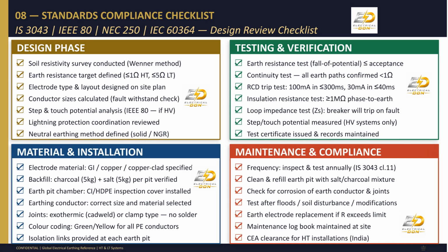Our compliance checklist covers the design phase, material and installation, and testing and verification. Key items include soil resistivity surveys, defining resistance targets, ensuring correct conductor sizing, proper backfill material, and mandatory annual inspection and testing to maintain safety compliance.